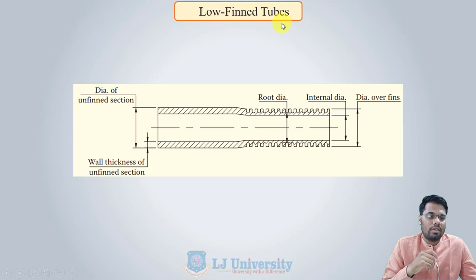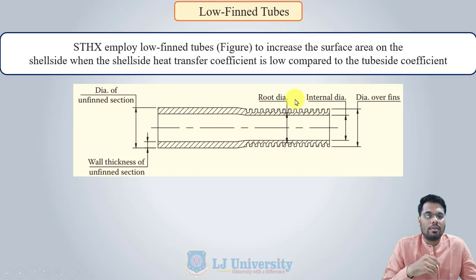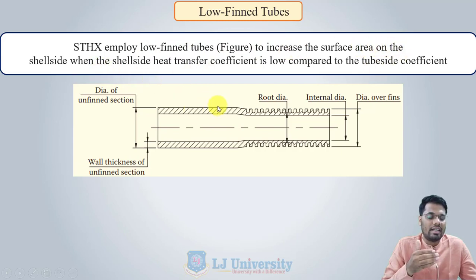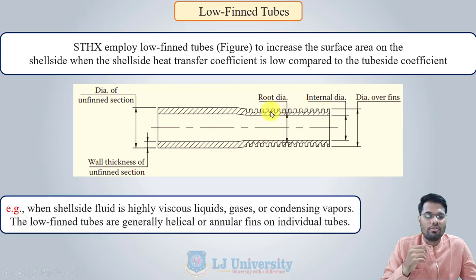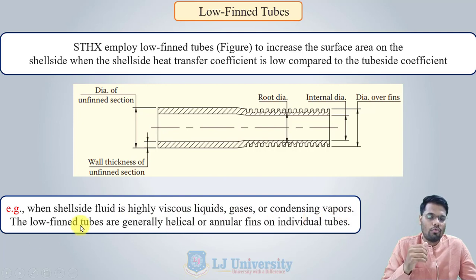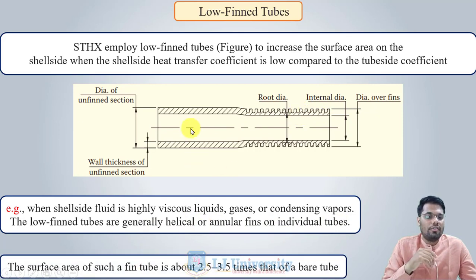Shell and tube heat exchangers employ low fin tubes to increase the surface area on the shell side when the shell side heat transfer coefficient is low compared to the tube side coefficient. This is especially applicable when the shell side fluid is highly viscous liquid, gas, or condensing vapour. Low fin tubes generally have helical or annular fins on individual tubes. The surface area of such fins is about 2.5 to 3.5 times that of bare tubes without fins.